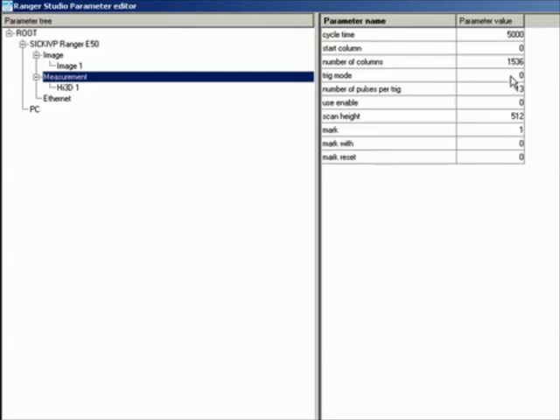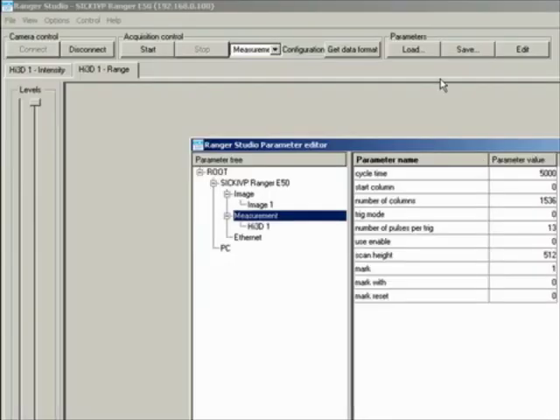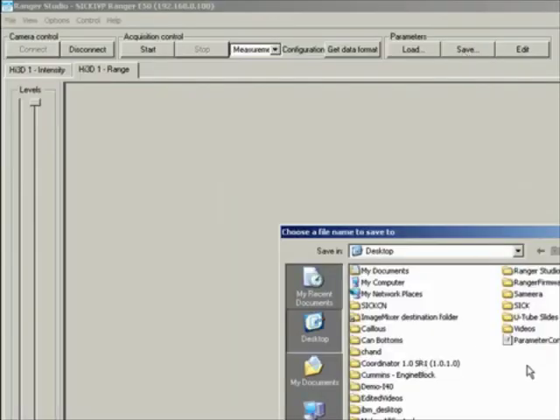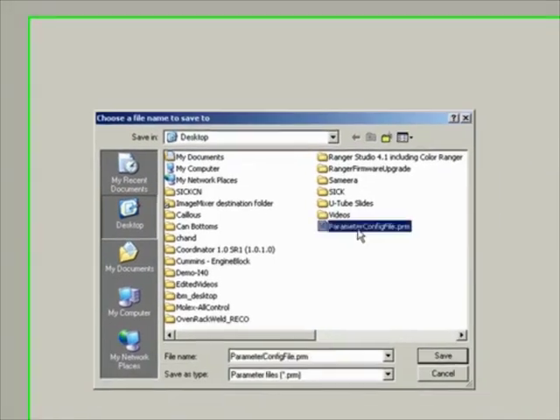In order to do the calibration, you must make sure that your parameter file has a trig mode of zero as well as the enable of zero, because you cannot have the sensor enabled or the encoder mode enabled when trying to do calibration. Once you have done your parameter file configuration and are getting a decent image, go ahead and save that parameter file — in this case, I will save it to the desktop.